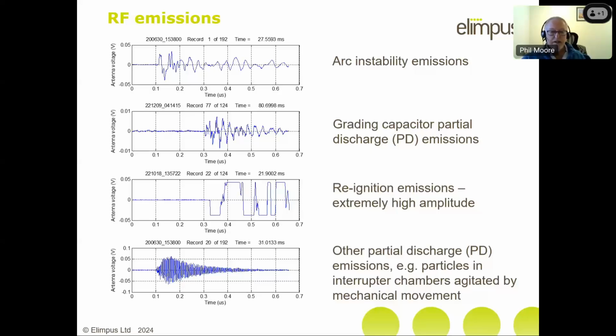Although, you know, all of these are large signals. Don't go thinking that they're difficult to measure. They're not. They're pretty big signals. So if you see that, then you know there's probably some issue going on internally to the interrupter. And incidentally, if some of you are saying, well, surely substations are just full of noise, you must see these all the time. Well, the answer is you do, but those signals only appear when the circuit breaker operates. So it's a pretty foregone conclusion that they're due to the circuit breaker.